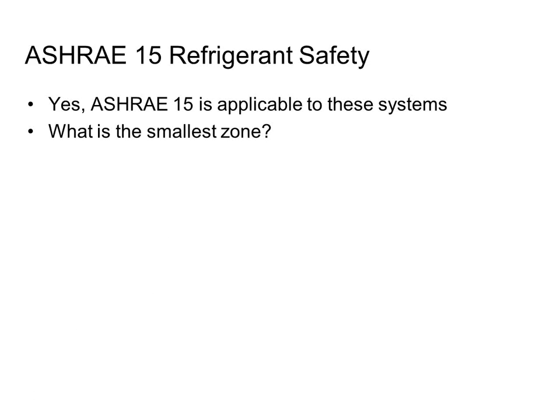The first question to figure out for either one of those 2 codes is who's my smallest zone? Because the worst case scenario is that all of the refrigerant in my entire system leaks into one tiny zone and someone dies, right? What's my smallest zone, so I know the smallest amount of volume I have to deal with in case my refrigerant leak was in fact in that room. Question number 2 is, how many pounds of refrigerant do I have in this system? If I have half a pound of refrigerant like you have in your refrigerator, it doesn't matter. If I have lots of pounds of refrigerant, it's going to matter. So how much do I have? So who's my smallest zone, and how many pounds of refrigerant do I have in my system?